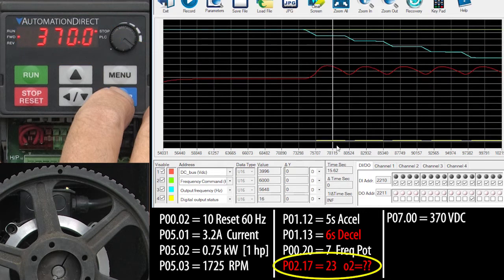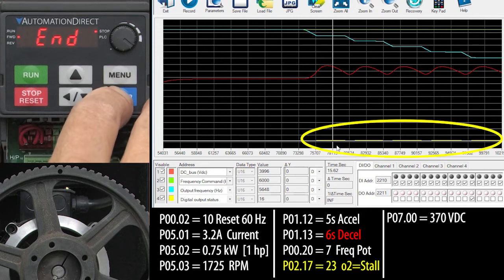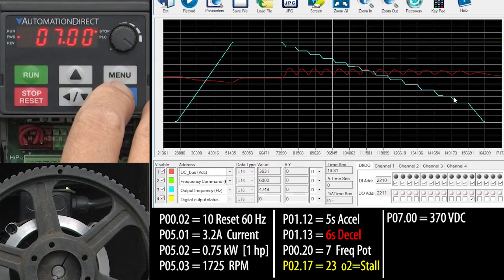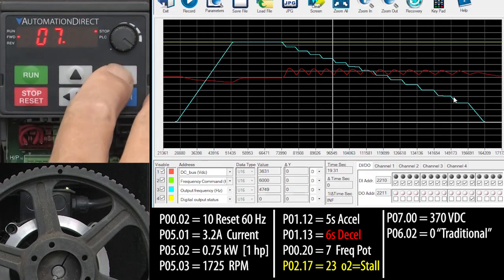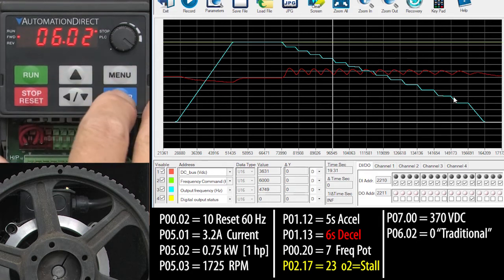And look at this, output 2, which I changed a minute ago, is now showing us every time the protection kicked in. Cool. OK, that's the drive's default protection method, which it calls the traditional overvoltage stall prevention and you set it in parameter 6.02.